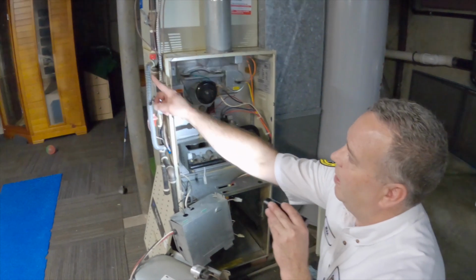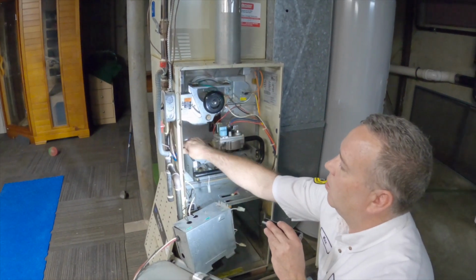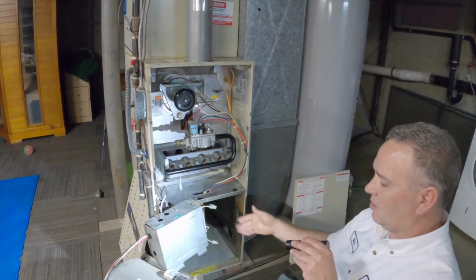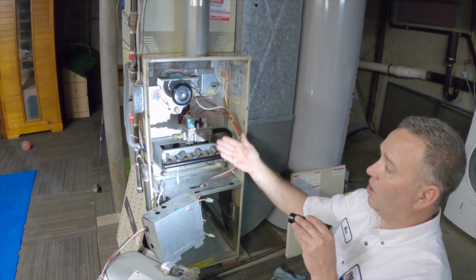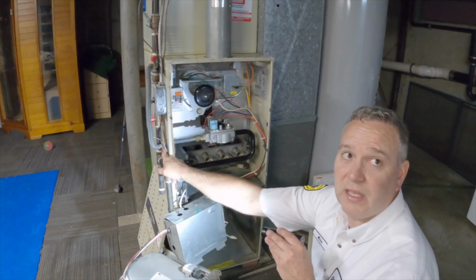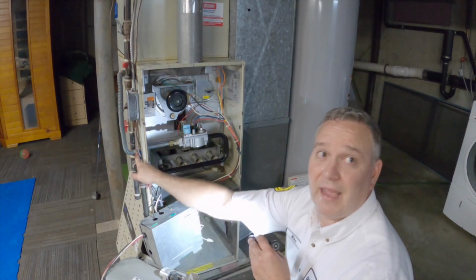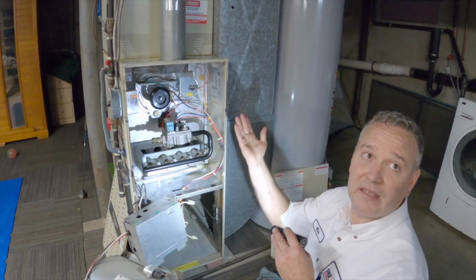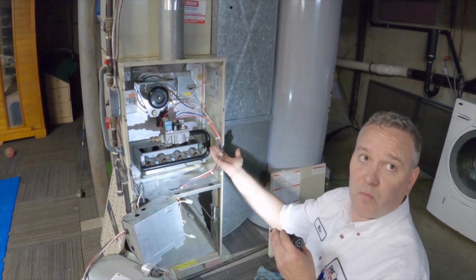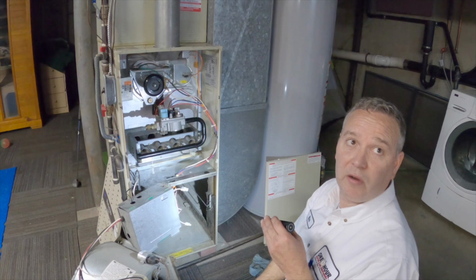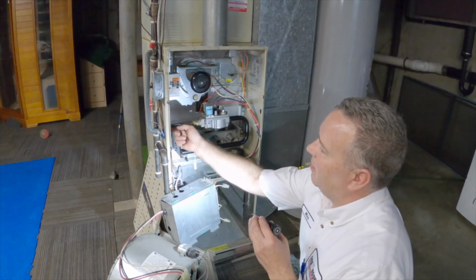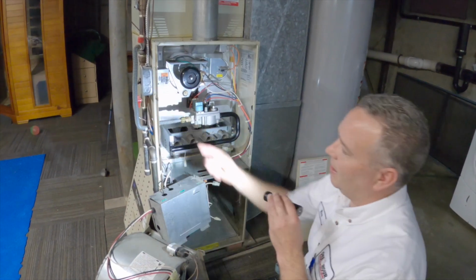But this flexible gas piping going through here, what can happen is if for some reason this blower gets off balance and the furnace starts to shake, it could sever this gas line. When it severs that gas line, what do you get? Gas leaking into the home. Even worst case scenario, cause a fire or an explosion. So that's definitely something that needs to be addressed and is not safe.